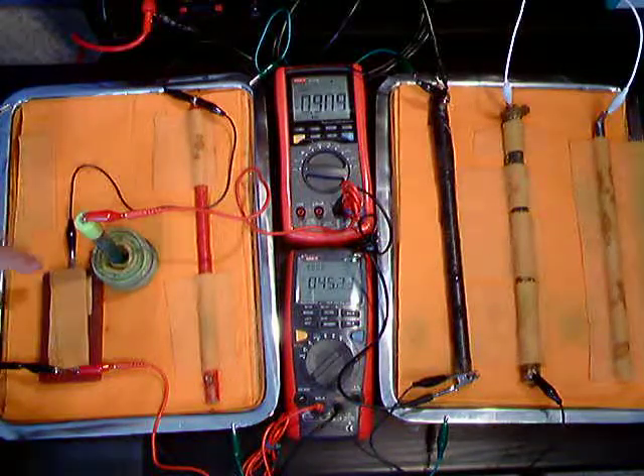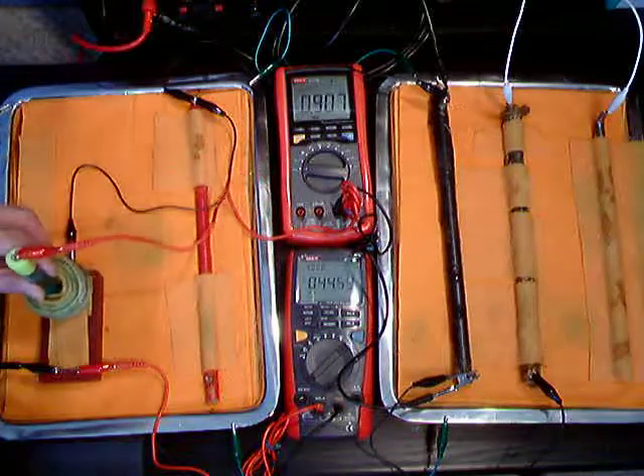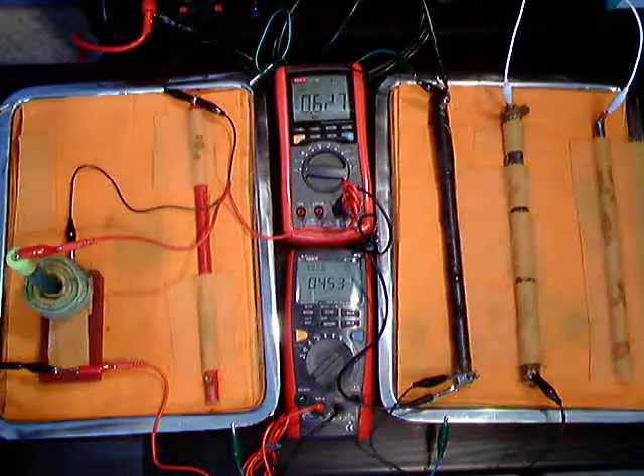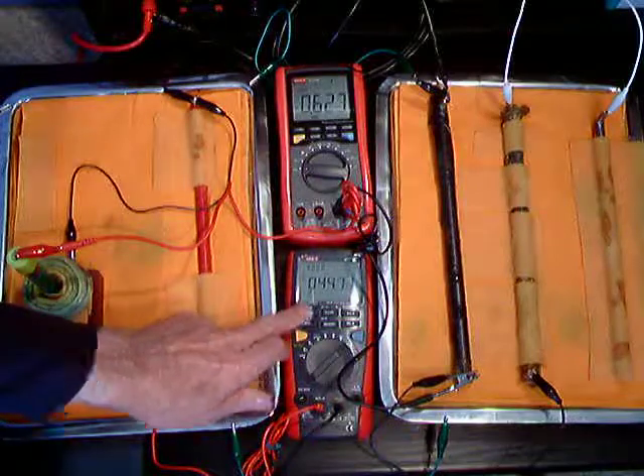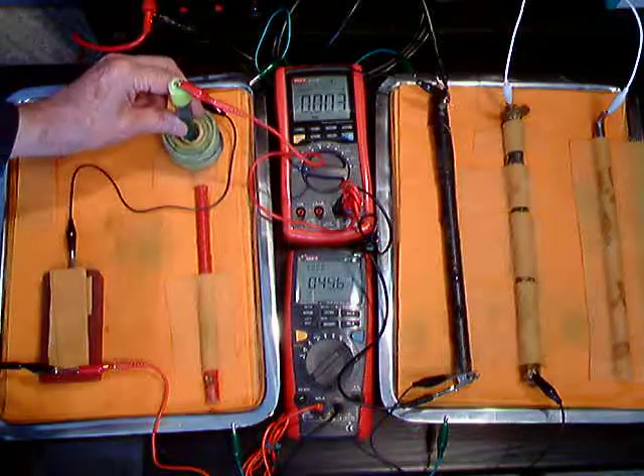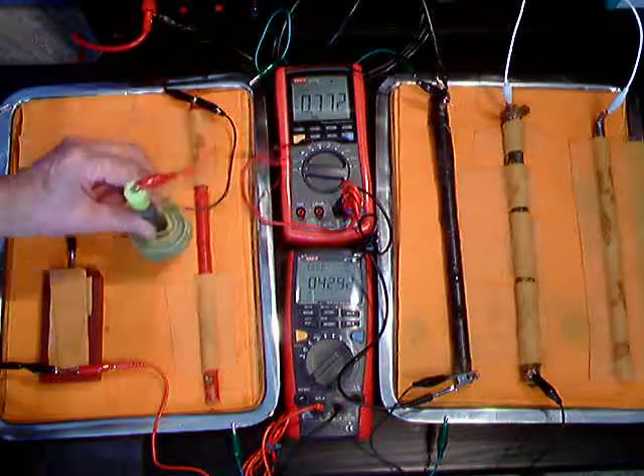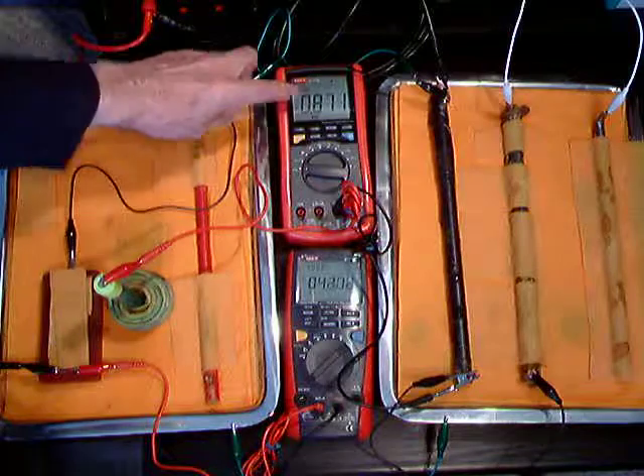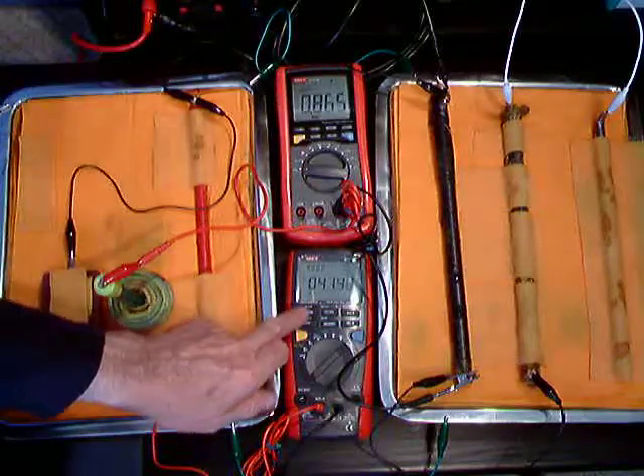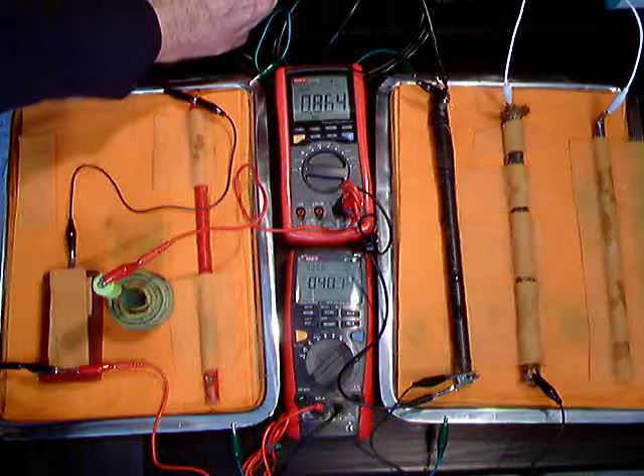When the half cell is put in the position that it is supposed to be in, the reading is even less, but the corrosion has still stopped. So it depends on the position of the half cell. The reading we get here at the half-cell can show that the corrosion has been stopped by the cathodic protection.